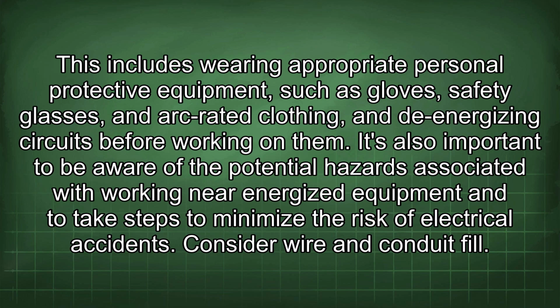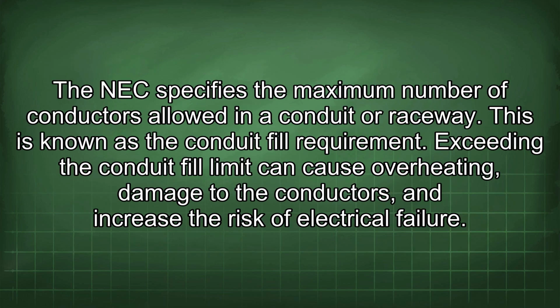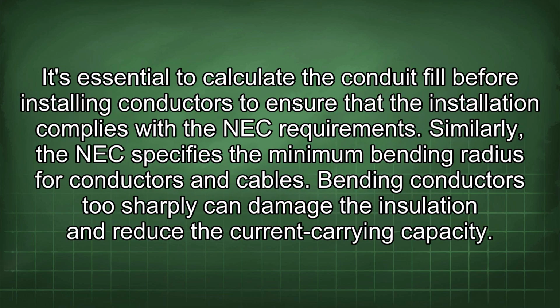Consider wire and conduit fill. The NEC specifies the maximum number of conductors allowed in a conduit or raceway. This is known as the conduit fill requirement. Exceeding the conduit fill limit can cause overheating, damage to the conductors, and increase the risk of electrical failure. It's essential to calculate the conduit fill before installing conductors to ensure that the installation complies with the NEC requirements.